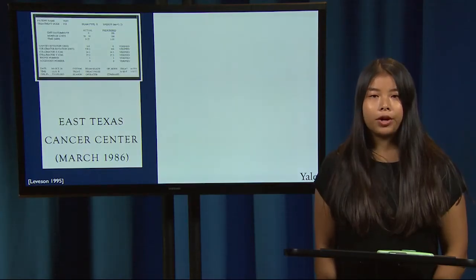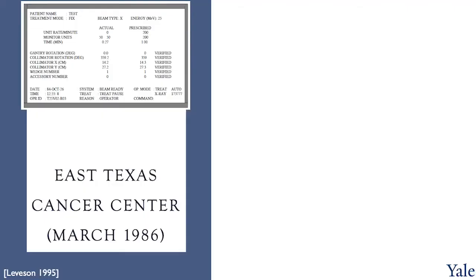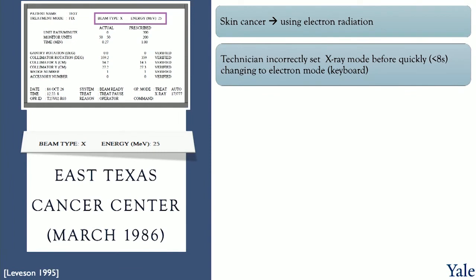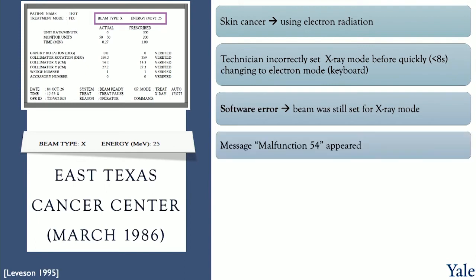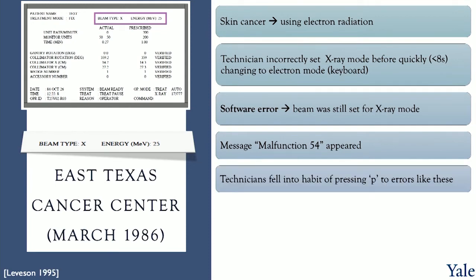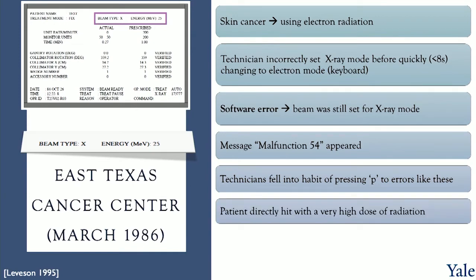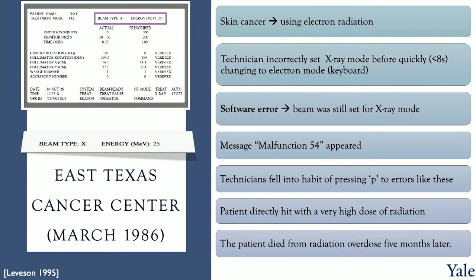Here's an example of a time when things went wrong. In March 1986, at the East Texas Cancer Center, a male patient came in for skin cancer electron radiation treatment on his back. He was going in for his ninth treatment. After sending the patient into the treatment room, the technician incorrectly set the machine on x-ray mode, but quickly changed it to electron mode using the up arrow key to edit. The parameters displayed as verified on the screen, and she hit the key to begin treatment. The software did not detect the last-minute change and left the beam on x-ray mode, even though the computer read electron mode on the screen. The machine quickly shut down and displayed malfunction 54 on the screen. There was no indication in the instruction manual as to what this malfunction indicated, and accustomed to the frequent stops and problems with the machine, the operator pressed the P key to proceed with treatment. It was later revealed that the patient had received a massively concentrated overdose of up to 155 times more radiation than planned. The patient died from resulting complications five months later.